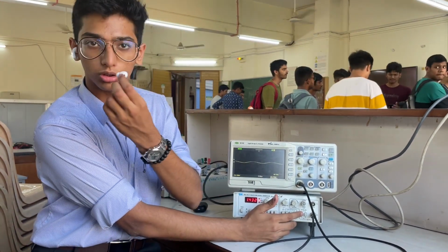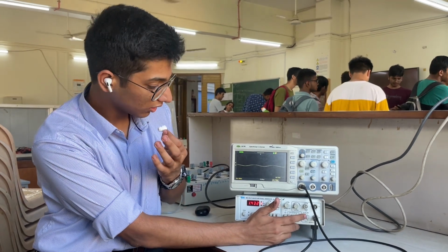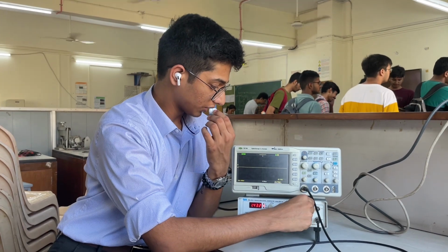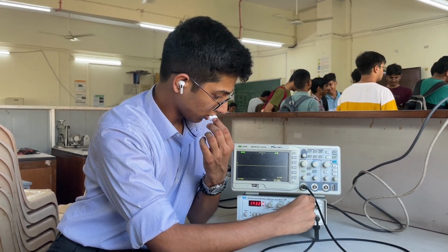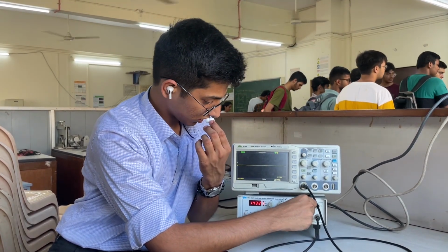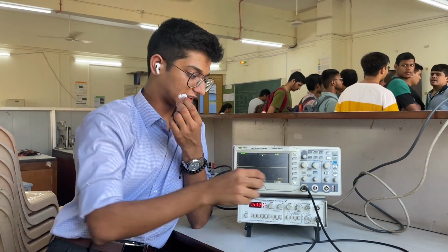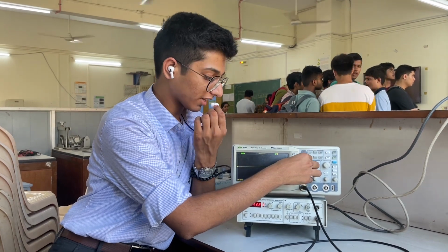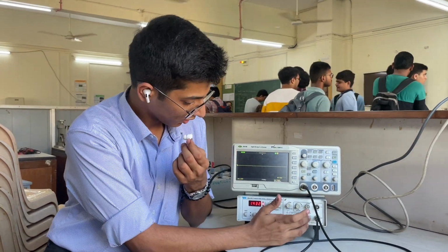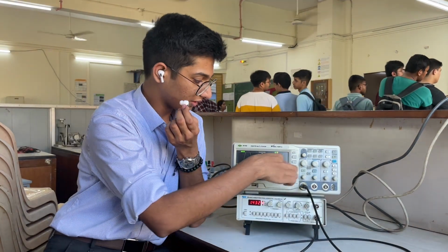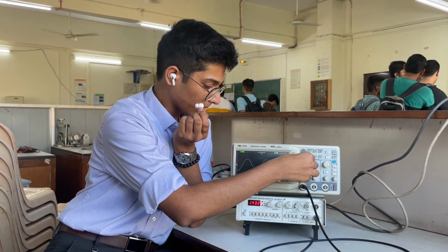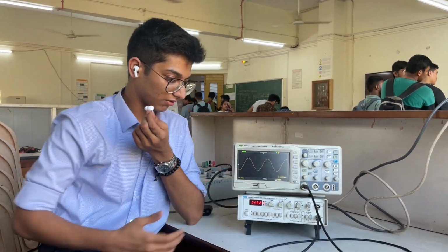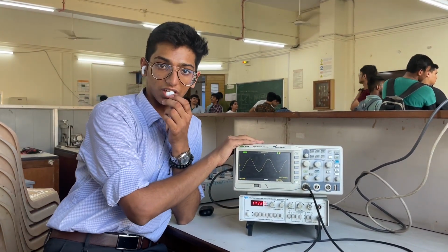And there is also another option to press both of them together, 20 and 40, which add up to 60 decibels, and it shows an attenuation of 60 decibels. Yeah. So if I adjust this, it's very small, so I can't adjust it anymore. Now, even if I adjust the horizontal one, I can't adjust it because it's too small. So that's that. So you close that, and you can see it has come back to its normal form. And I had changed the grids because I had to decrease it so that I could adjust the sine wave. And so this is how a function generator works.